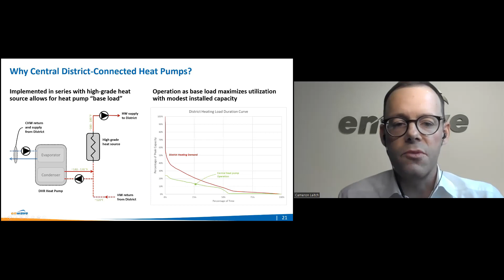As noted previously, the 3 district heat recovery plants that are the focus of this presentation have been configured as base load heating assets. DHR Plant 1 is nominally 1,350 tons, composed of 3 high lift centrifugal chillers. Its design basis was to provide 135 F leaving the condenser, while producing 39 F leaving the evaporator. DHR Plant 2 is a single nominal 200-ton screw compressor chiller. It can produce 140 F heating water coincident with 40 F chilled water.